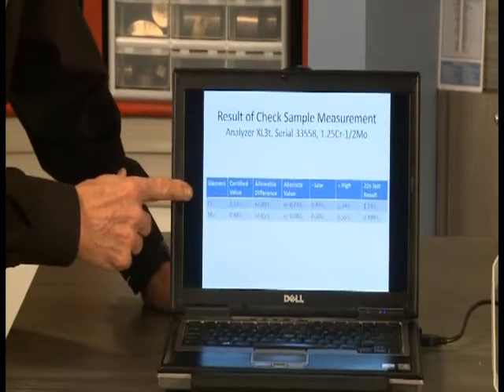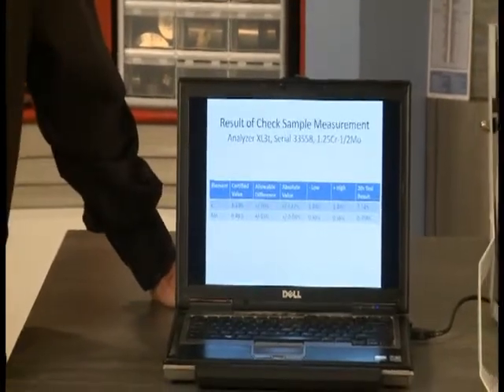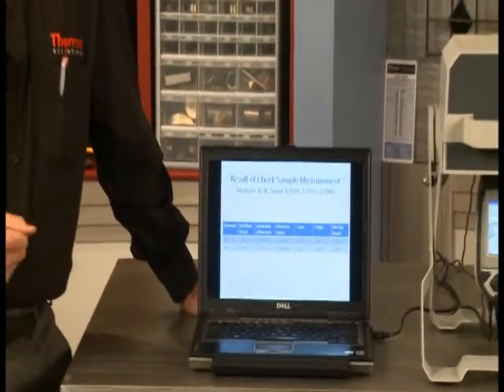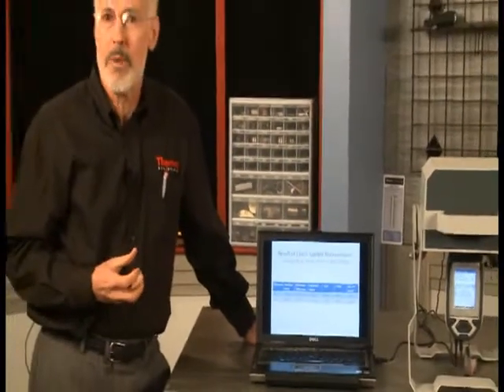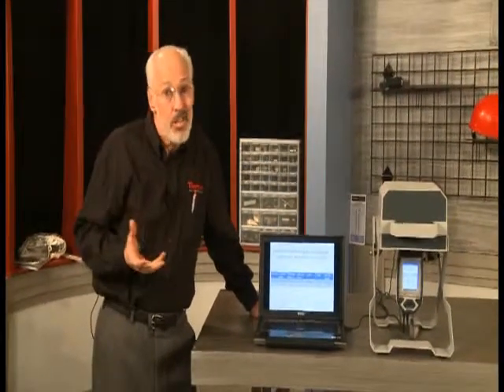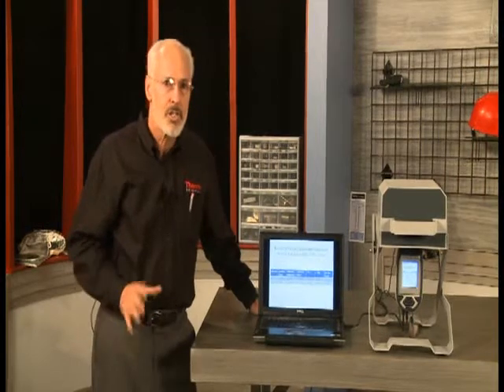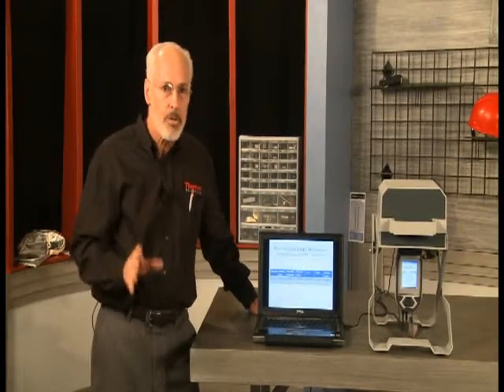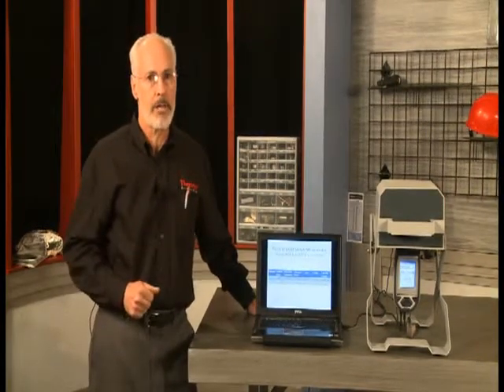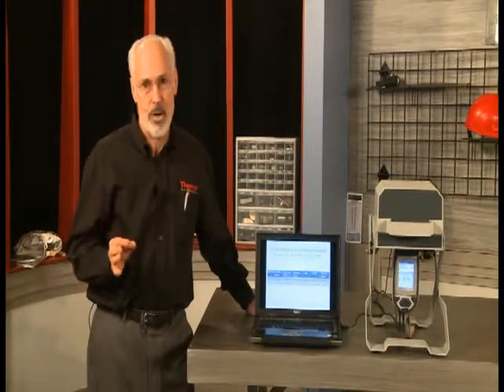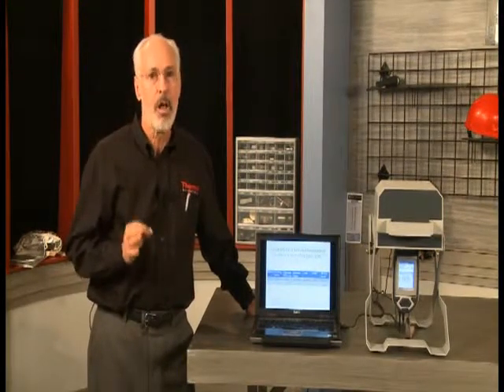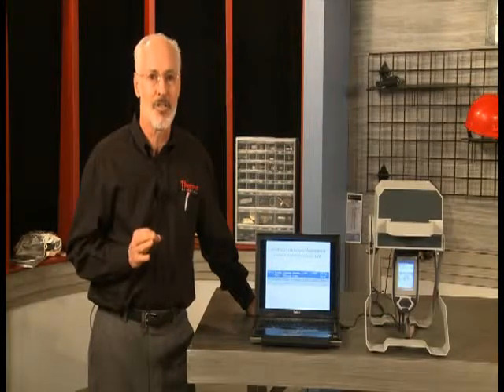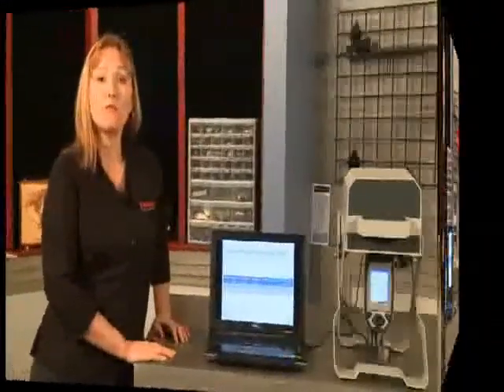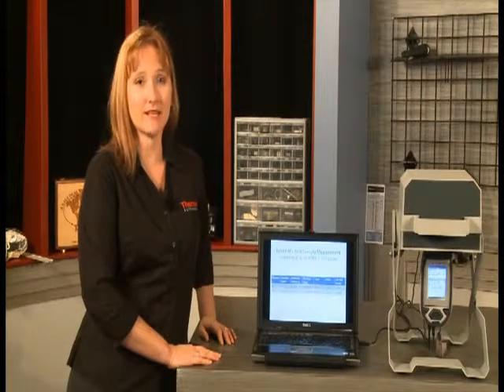If either of these values is not within the required tolerance, retest the check sample for another 20 seconds. This will eliminate the possibility that the previous shot was a statistical anomaly. If the result is still outside the expected boundary 2 times in a row, the calibration is not correct. In this case, perform a detector calibration and retest the check sample. Should this not bring the result into the required range, please contact your local Thermo Scientific Niton Analyzer Service Department for assistance.